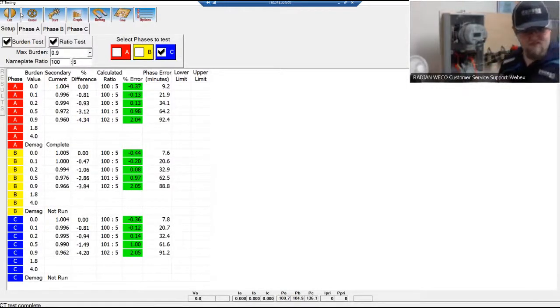So there's no difference on the software end and how to run the test on the Bantam. The only difference being you can only do one phase at a time. If you try to select A, B, and C, like what I did with the RW, the check mark will move whichever one you click. It will only allow you to choose one. It's because with the TSBR1, we have the one duckbill and the one voltage connection. Voltage connection doesn't need to move, but the duckbill will per phase.